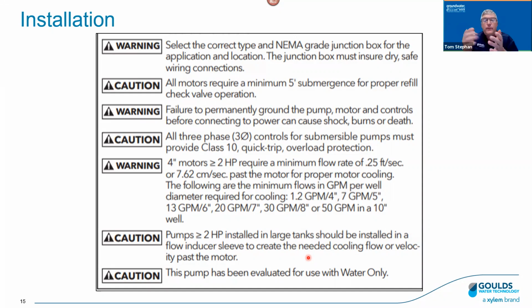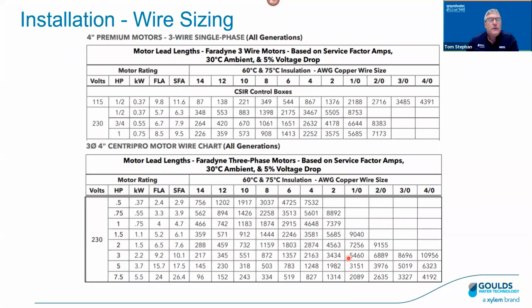If we have, for example, a 4-inch pump in a 5 or 6 inch well, that's a bottom feeding well, the water comes up past the motor and cools it. So that's probably what we would consider more of a normal type application. But if you put that pump in a large tank, for example, maybe it's a 2-pump system in a low yield well, then we have to make sure that water flows past the motor in order to cool it properly.